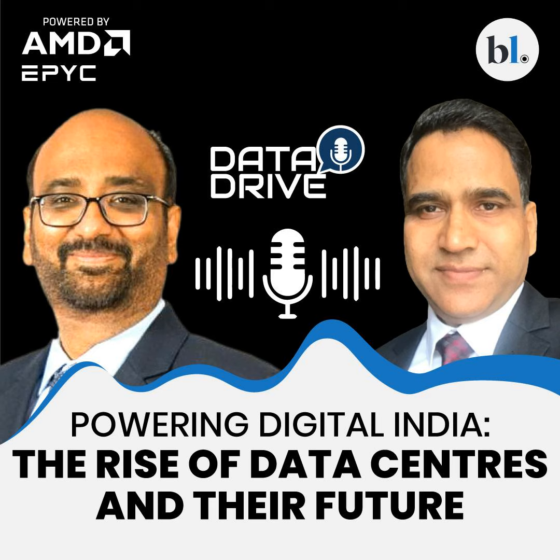Typically, if you talk about data center efficiency, which is measured in PUE, in Europe you find a lesser PUE for data centers. Also, there are a lot of big data centers by technological giants set up there only to take that advantage. In our case, the PUE is higher because our ambient conditions across the country are very high. Average PUE is around 1.5 to 1.6, which we achieve.